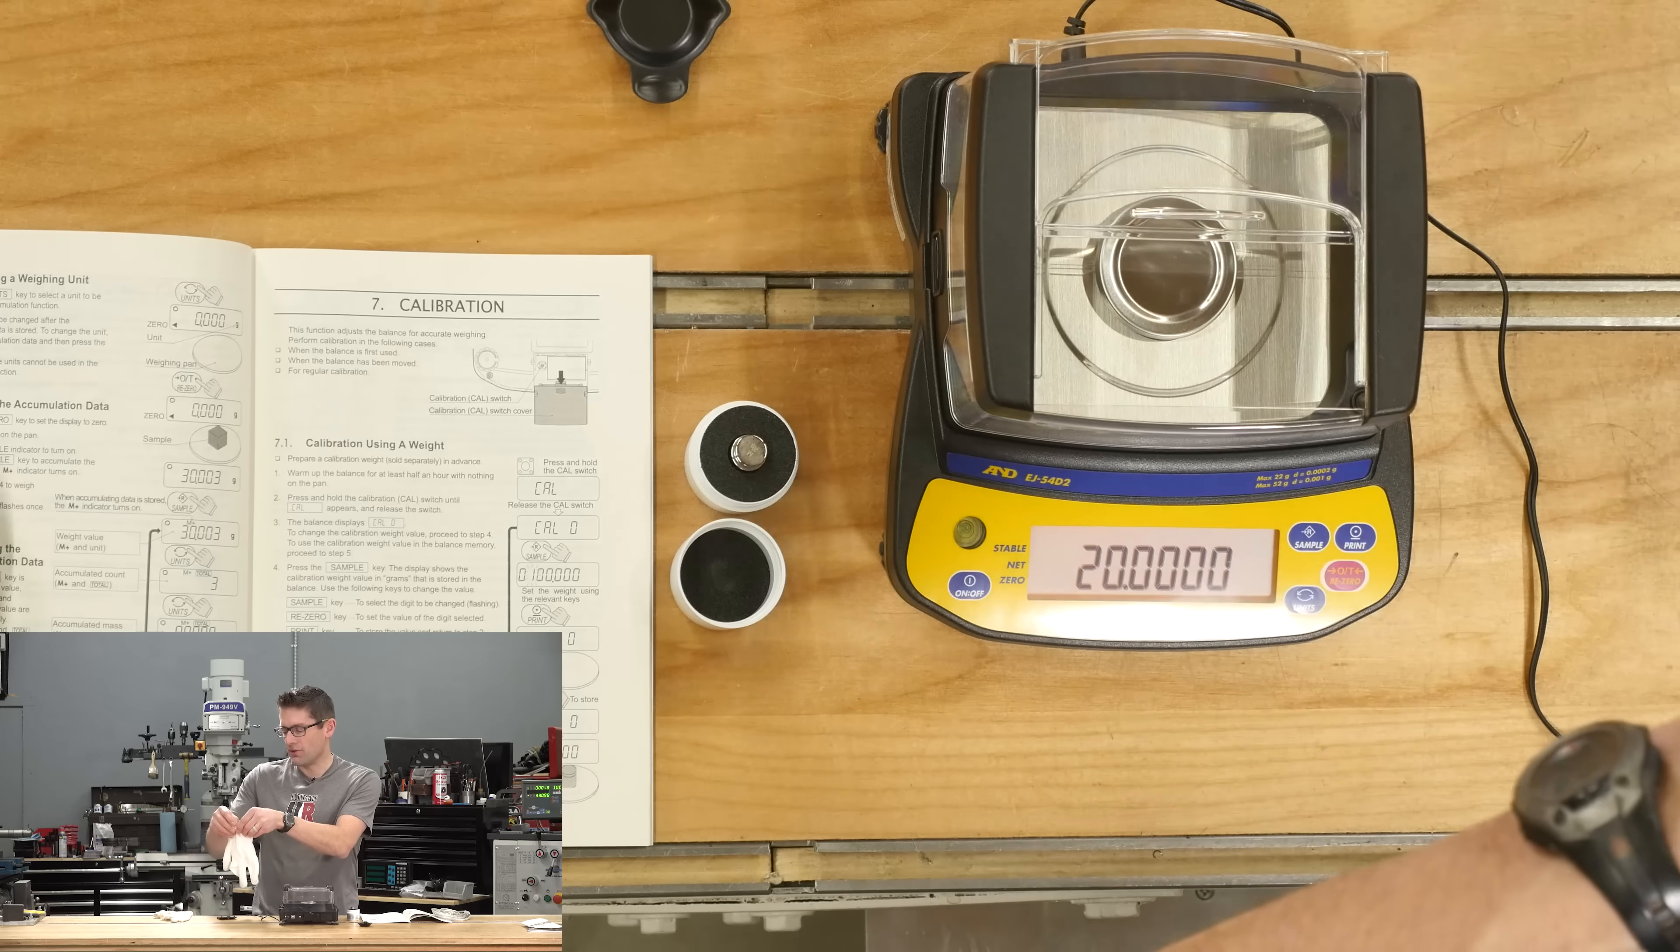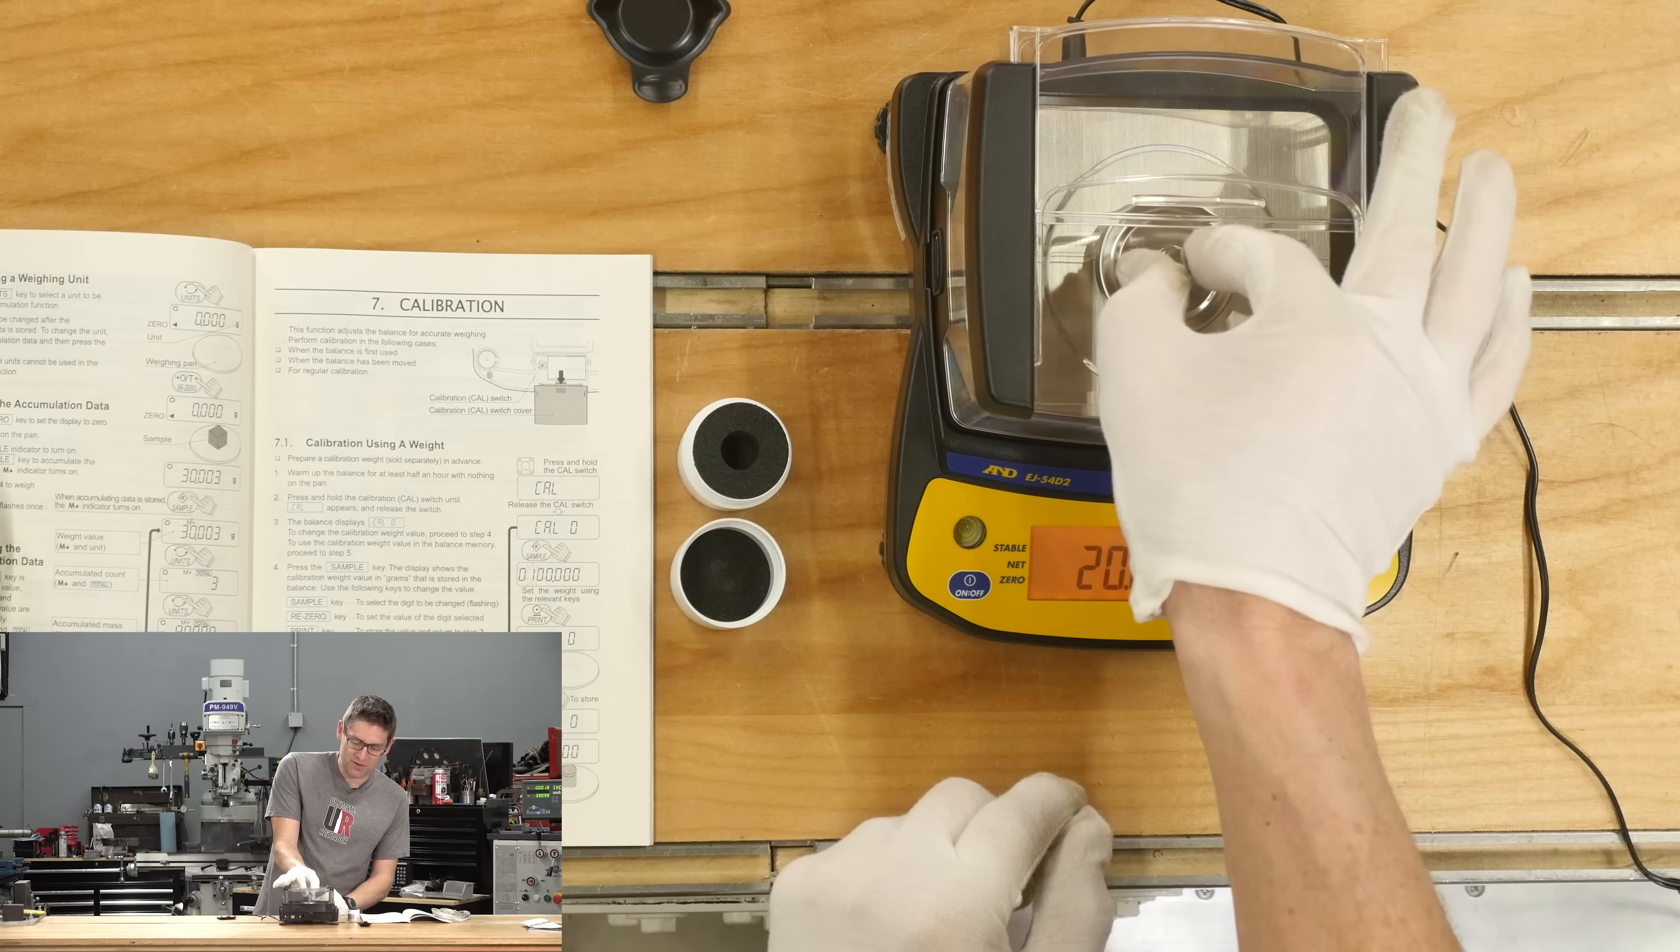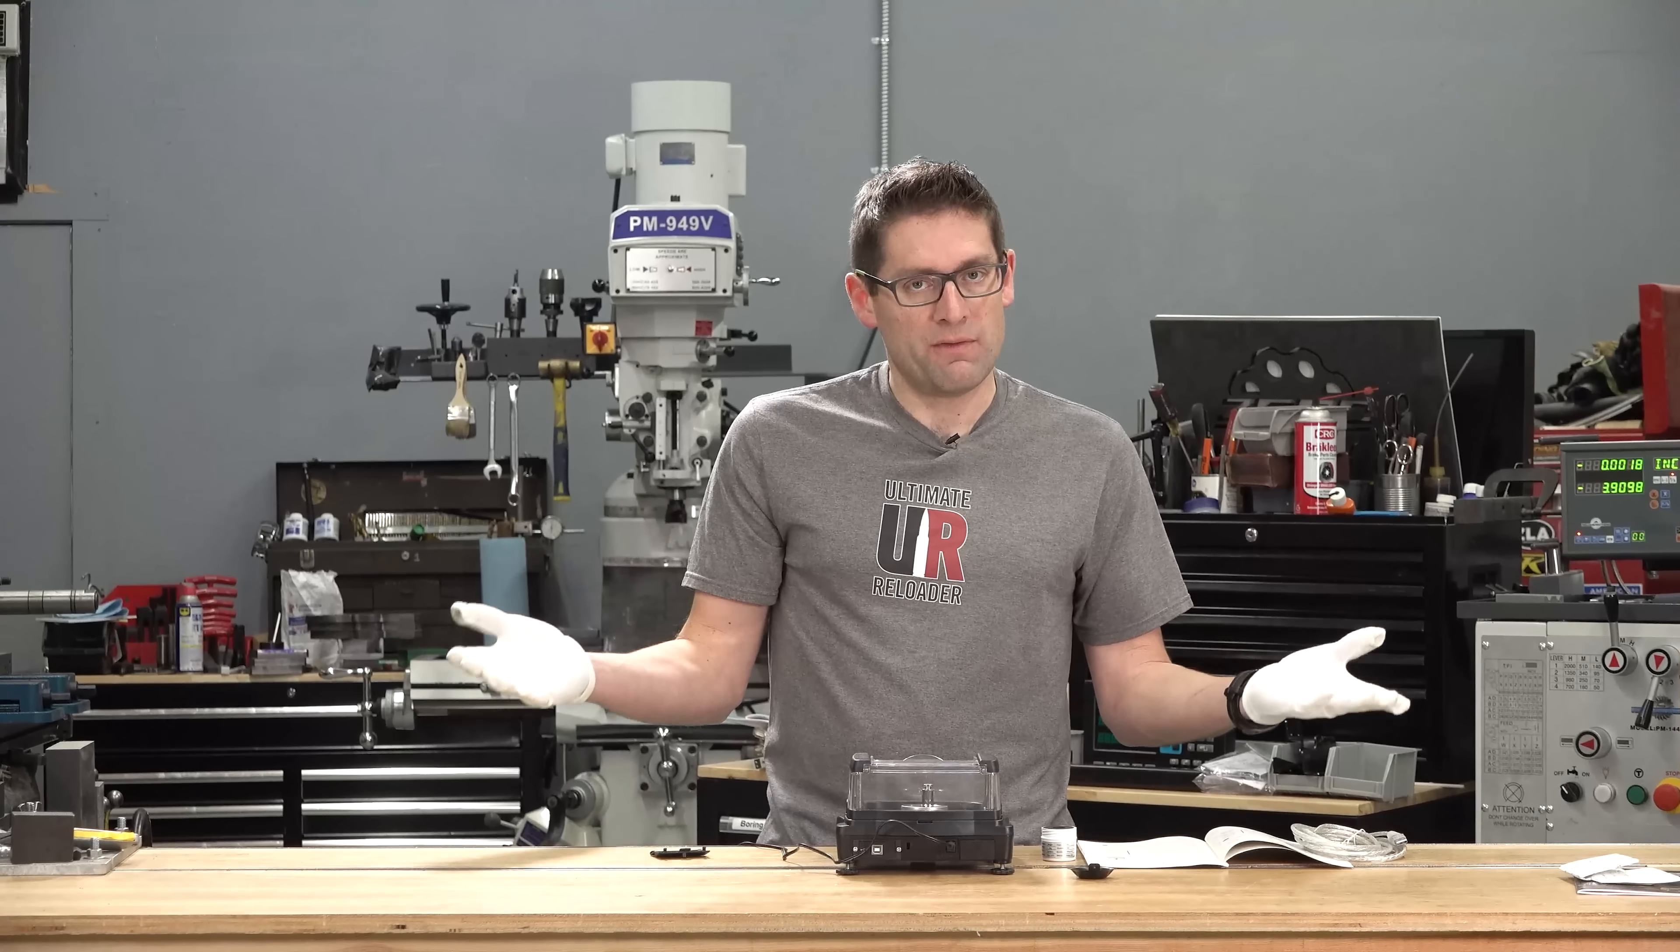Now, just to be extra sure that I'm being above board here, I'm going to put on my white gloves, because we don't want to get finger oils on this calibration weight. Sounds a bit excessive, but we are talking about an ultra-precision weight here. We're going to close the windscreen and then hit print again. It says end now. Now we can turn the machine on, and we should be fully calibrated.